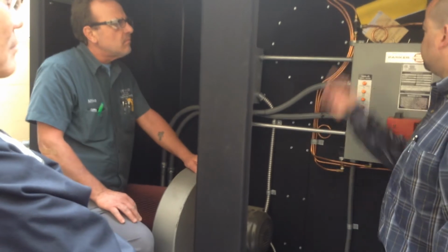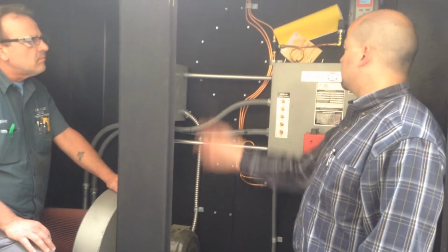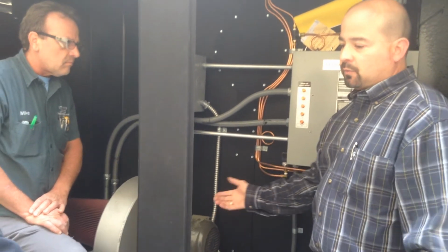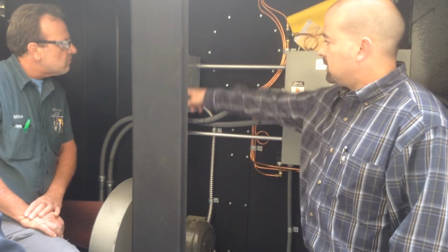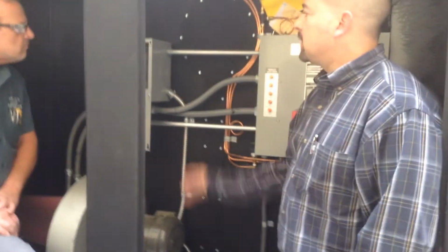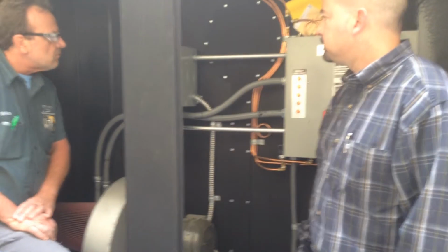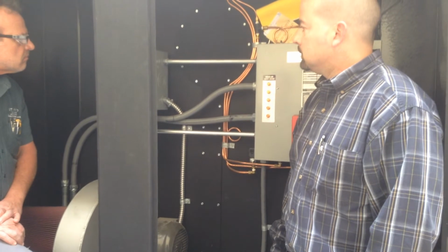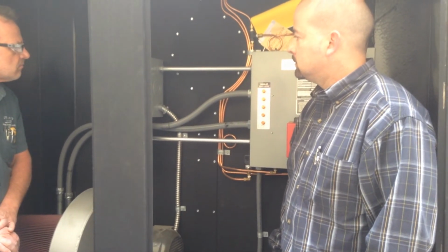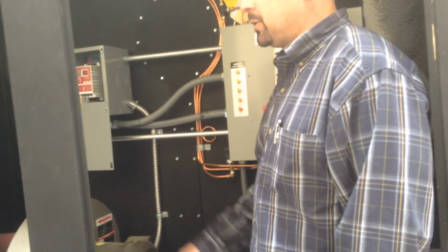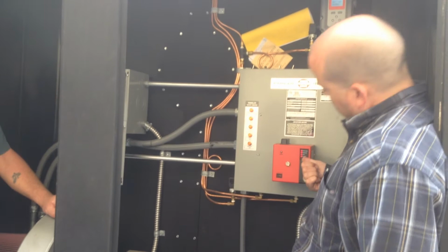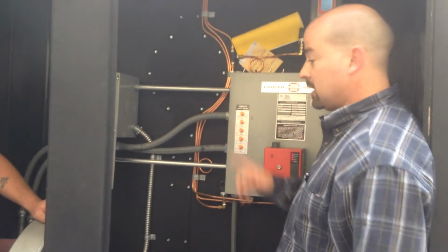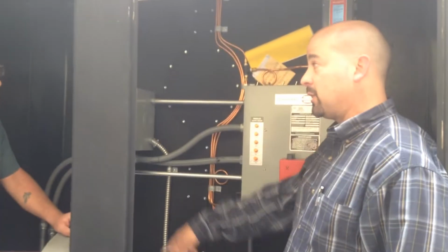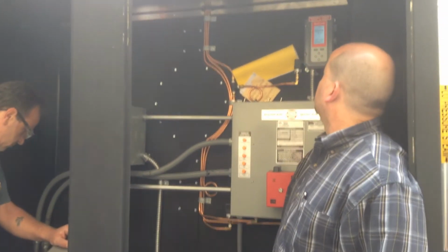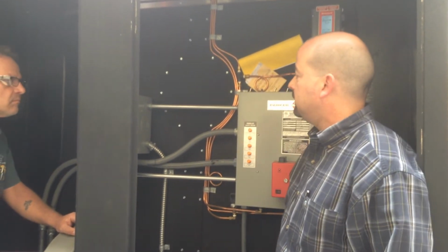You're at 0 psi. Turn on your switch. Turn on your burner switch. Blower comes on, ramps up slowly. You'll see the hertz go up. Goes up to what we set it for on pre-purge. So your pilot just turned on. Your pilot's going to prove when the flame light comes on, that means you've got a flame on your pilot. Your main just came on, so it's firing up, still ramping into high. We got a half a pound on the boiler right now.